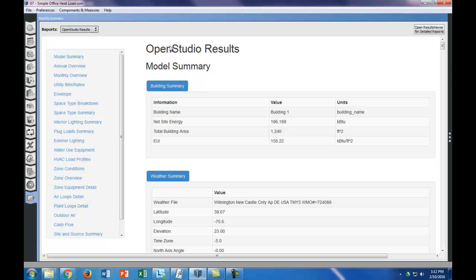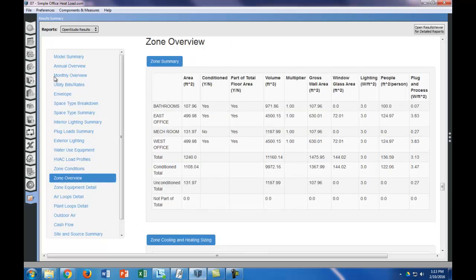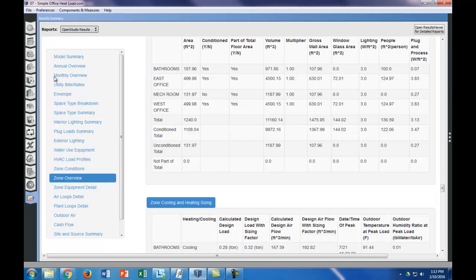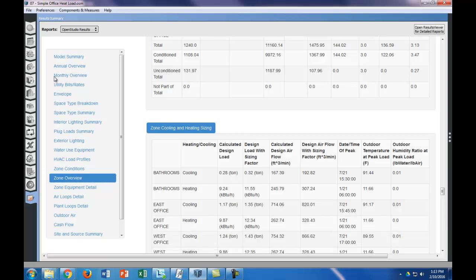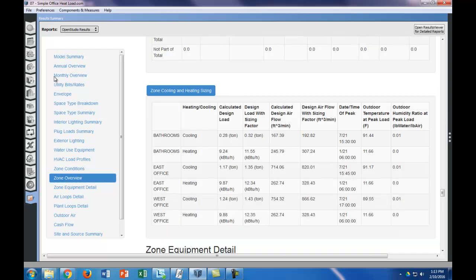So for this case, we're just looking for the heating and cooling load. And really what we want to know is since, when we did it by hand, really what we were trying to calculate was we were trying to calculate the size of our heating unit and the size of our AC unit. So we can actually get that under zone overview. And if we go to zone cooling and heating size, then we can really get to here how big our zone heating and cooling size is. This gives us the calculated design load and the design load with the sizing factor. And all the sizing factor is, is just like a safety factor, basically. So you're just increasing it by a certain percentage to oversize it just a little bit, so that way you make sure that it actually will meet those tougher times, especially if some of your assumptions weren't exactly correct.